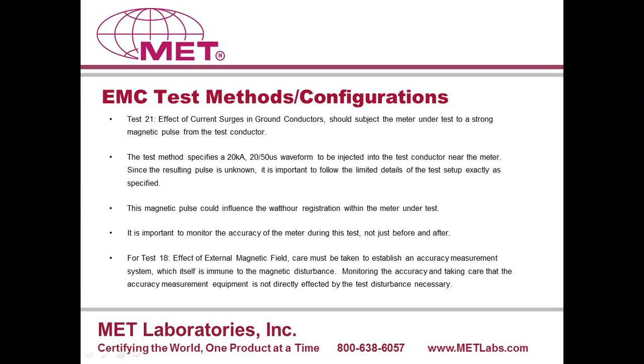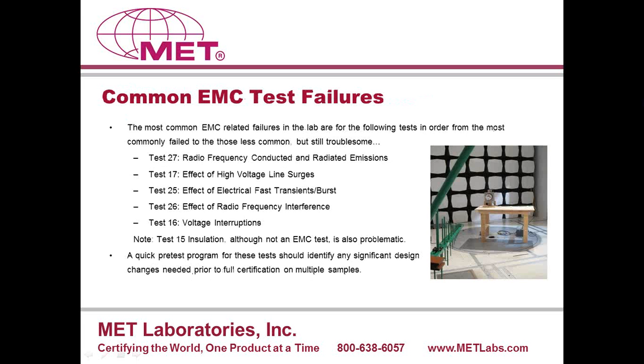Now, some of the common ANSI tests that we see failures for are test number 27, radio frequency conducted and radiated emissions, effect of high voltage line surges, electrical fast transients burst, radio frequency interference, and voltage interruption. These are listed in the order that we see the most failures for. Test number 15, insulation test, although it doesn't typically fall under the ANSI test category, sometimes we also see some issues or failures with that test as well.